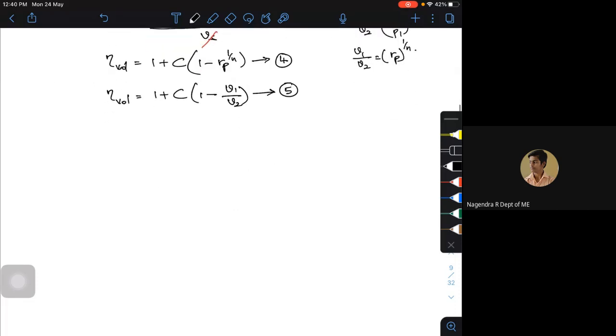Okay, volumetric efficiency in terms of ambient conditions. We call that free air delivered. Free air delivered means, say I consider the ambient temperature as 15 degrees and the ambient pressure as 1.01325 bar. What is the amount of air delivered at that condition? We call that free air delivered. And the volumetric efficiency based on that particular condition is called volumetric efficiency on ambient conditions.